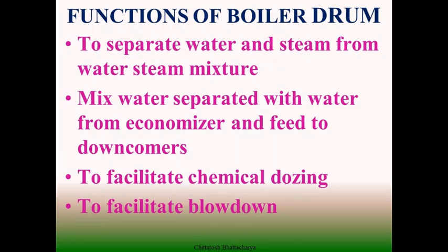The typical functions of the boiler drum, as we have already discussed, are to separate water and steam from the water-steam mixture generated in the water walls, mix the separated water with the water from the economizer and feed it to the downcomers, and see that there is no vortex formation in the drum and that the level is maintained within the drum.